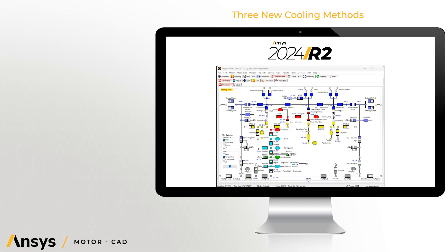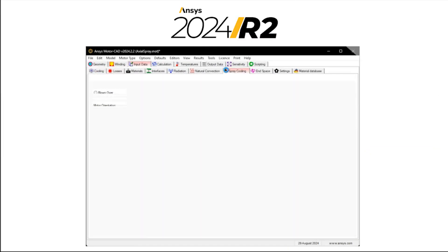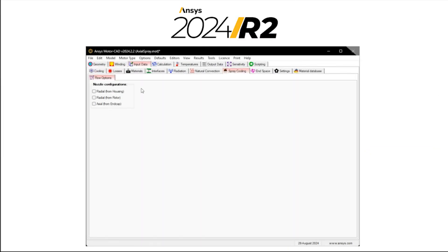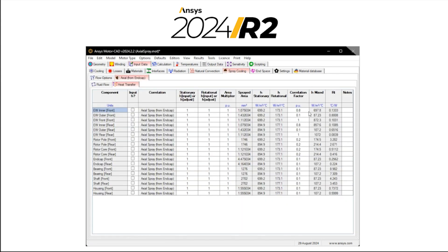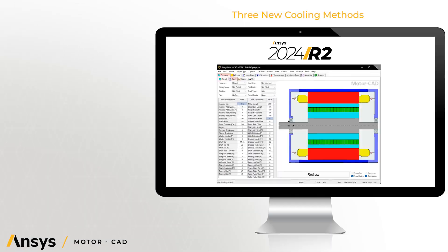Another cooling method added is the Axial from Endcap spray cooling option. It uses experimentally derived heat transfer coefficient correlations for oil impingement from shaft and rotor end surfaces. It can be run in combination with radial from housing and radial from rotor spray cooling options.